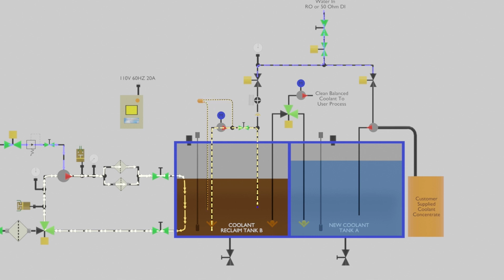If the coolant concentrate in Tank B is higher than the set point in the auto balance controller, the Tank B 24-volt inlet water solenoid will open, sending water into Tank B for dilution. A flow totalizer shown here will then measure a pre-programmed amount of water and then shut off Tank B 24-volt inlet water solenoid when that amount has passed across it.